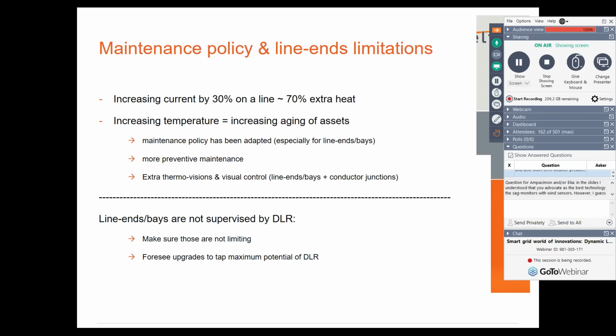If you increase the conductor capacity, you have to be sure that the bus bay can cope with those higher loads. And so sometimes you have to make some investment to replace or upgrade the line ends also. You also have to adapt the protection because sometimes you will see higher current and you have to adapt the set point of the protections. This is mostly software, but you have to also think about it. So in practice, you have more steps than just installing a little box on the line. But if you do it properly, you will manage all the risk and you will be in control of this technology.